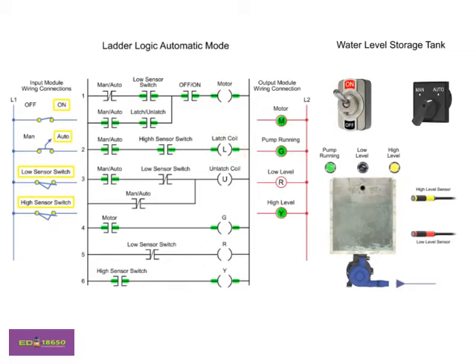As water is discharged from the tank, the high-sensor switch and high-level lamp is turned off. Water falling below the low-sensor switch stops the discharge pump motor and turns on the low-level red lamp. The automatic cycle waits for the tank level to reach the high-sensor switch to begin the cycle again.